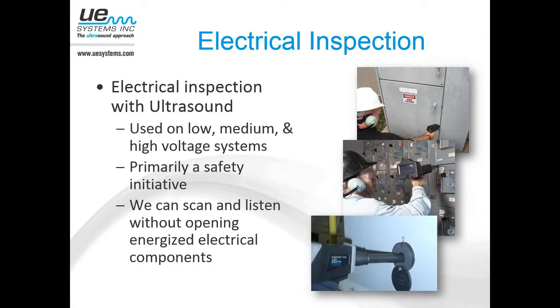So we can use that on any voltage - it's not really voltage dependent. Primarily, people start out with ultrasound as a safety initiative. If you work around electricity, there's always the potential of an arc flash incident when you open enclosed cabinets or enclosed switchgear. Even when completely outfitted in proper PPE, you may avoid serious burns, but if you're involved in an arc flash incident, it could throw you across the room, and maybe the burns aren't your biggest problem - maybe breaking a shoulder, an arm, or worse.